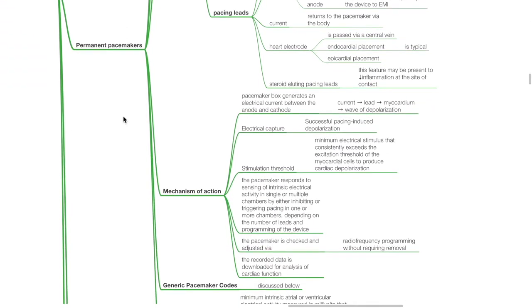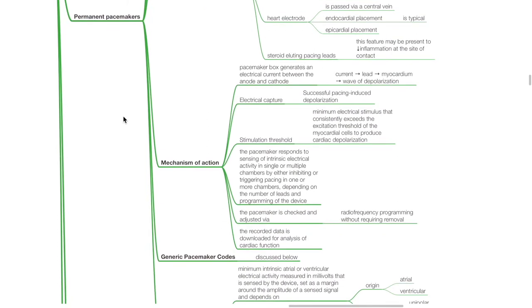Mechanism of action: the pacemaker box generates an electrical current between the anode and the cathode. Current travels via the lead to reach the myocardium and initiates a wave of depolarization and contraction. Electrical capture refers to successful pacing-induced depolarization. Stimulation threshold refers to the minimum electrical stimulus that consistently exceeds the excitation threshold of the myocardial cells to produce cardiac depolarization. The pacemaker responds to sensing of intrinsic electrical activity by either inhibiting or triggering pacing depending on the programming of the device. The pacemaker is checked and adjusted via radiofrequency programming without requiring removal.